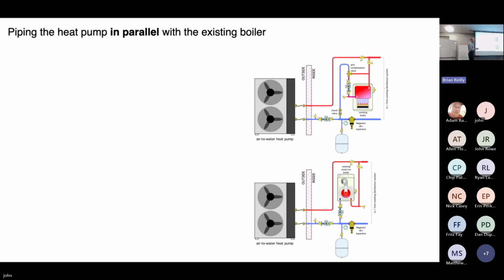Now the boiler itself, if it's cast iron, could have 6, 8, maybe even 10 gallons of water, but it's still a small amount of water compared to what the mass is out here. So it is designed to protect the boiler from sustained flue gas condensation. This is important if you're retrofitting. There are other ways to do this with motorized mixing valves, but the reason I stress that it's important, you may have a distribution system that's operated at relatively high water temperatures for years and everything's been fine.